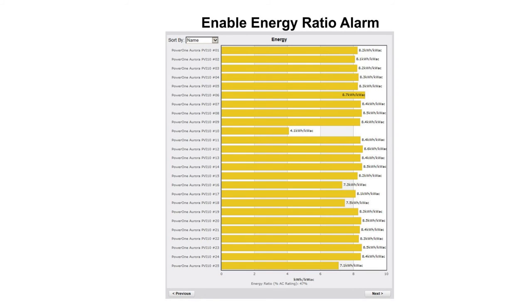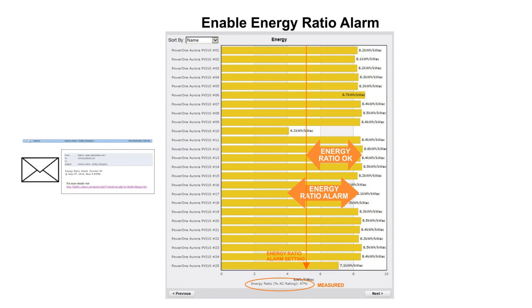To save having to frequently access the SolarView portal and inspect the output graphs, SolarView has an energy ratio alarm that can be set to email a warning when a potential problem is detected. Log in to setup with the site username and password to enter a suitable alarm level that is less than the normal variation between inverters. At the end of each day, SolarView will check and email a warning if it detects an energy ratio below the alarm setting. With automatic analysis, problems are detected immediately and fewer routine system checks are required.